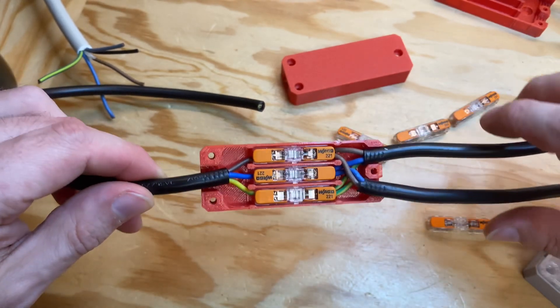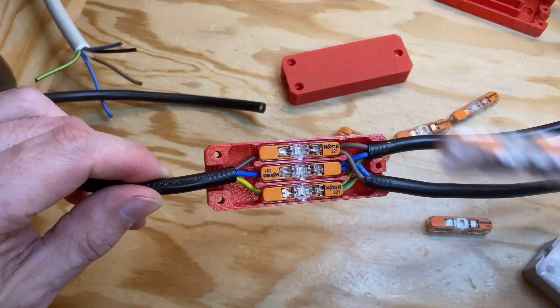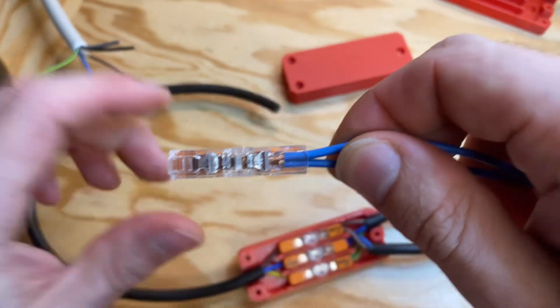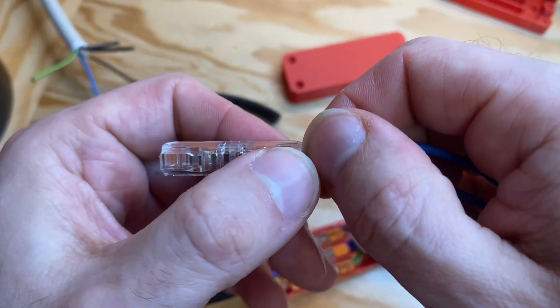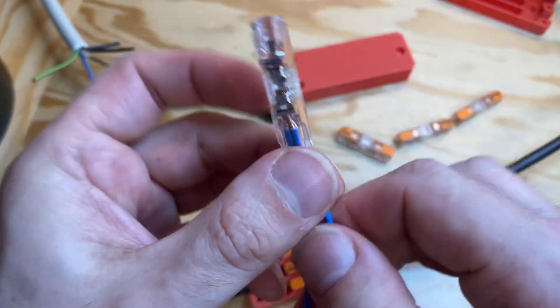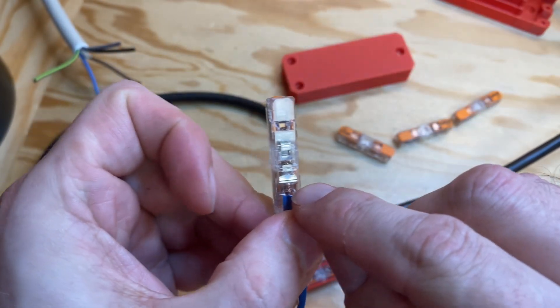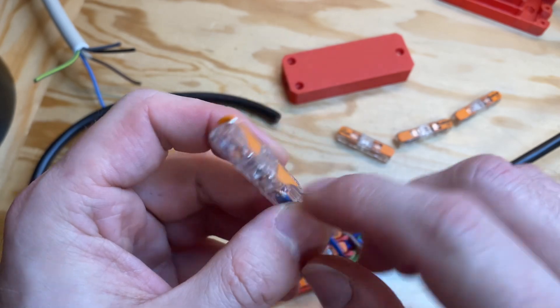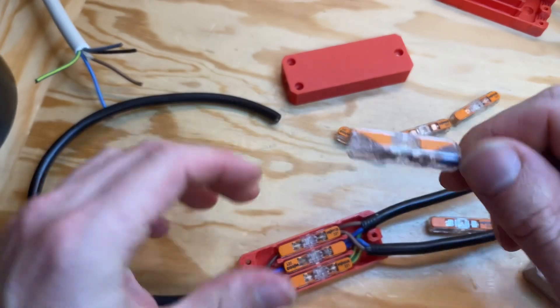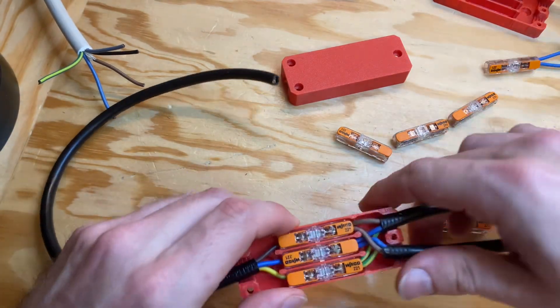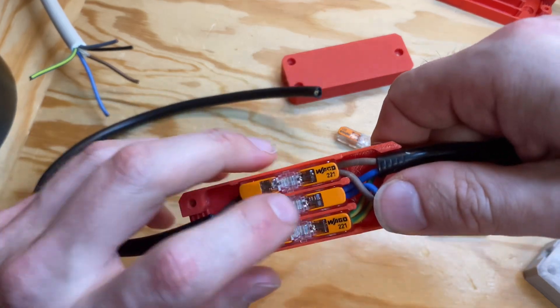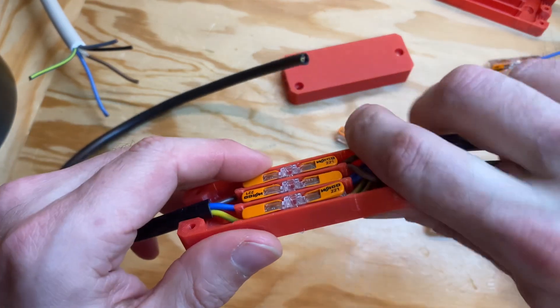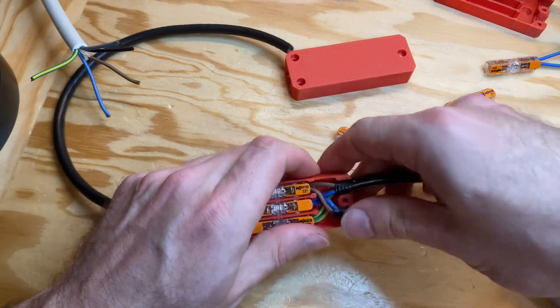In this design I'm cheating a little, because I'm actually connecting two wires into the same hole. Which you can do if it's stranded wires, but you can definitely not do it if you use solid wires. And there's of course a limit also on how much you can put into a single hole. It's four square millimeters.